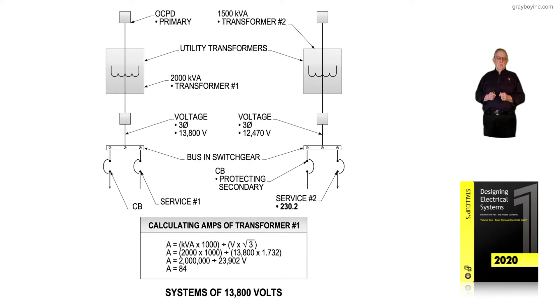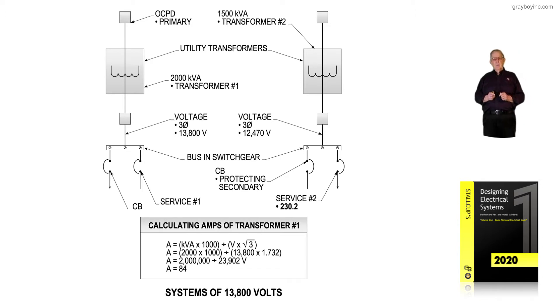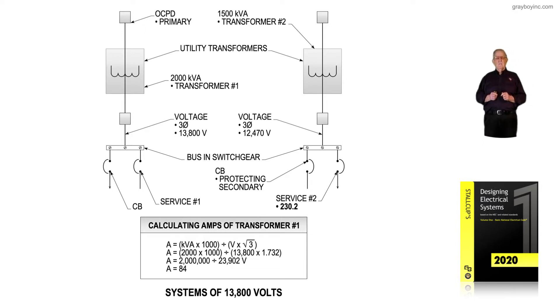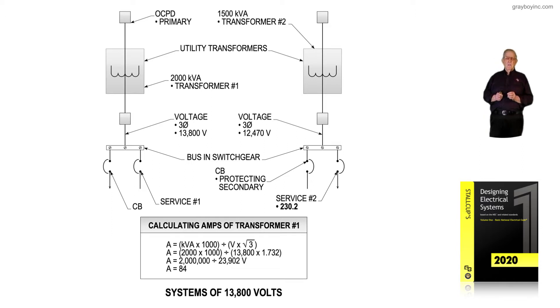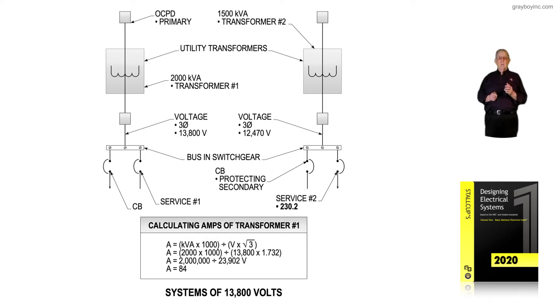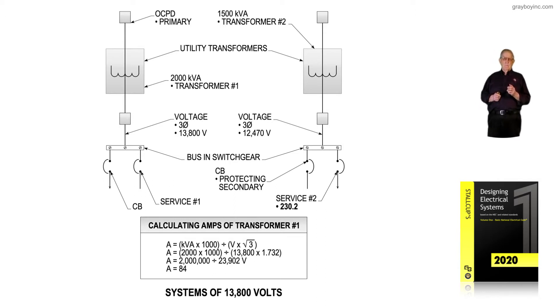This illustration deals with systems of 13,800 volts used in usually larger industrial plants and facilities. Notice the transformer to the left is a 2,000 kVA, three-phase, 13,800 volt. To determine the calculating amps of transformer number one, we take the kVA times 1,000 divided by the voltage times the square root of three. When the math is done, that gives us 84 amps.